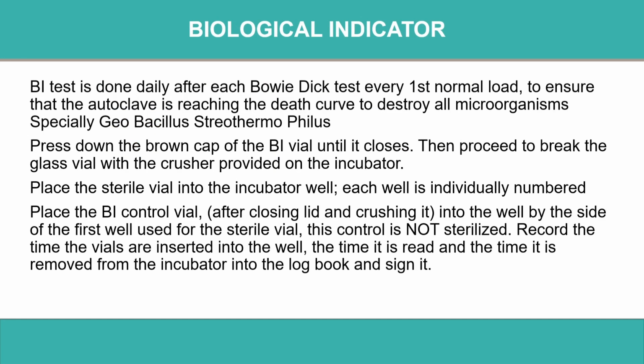These are the biological indicators. Actually, in the biological indicator there is a bacteria called Geobacillus stearothermophilus. This is a highly potent, highly heat-resistant bacteria that can tolerate heat. In the autoclave, the temperature goes above 134 degrees centigrade, and this is the bacteria that tolerates this heat. If we put it inside the incubator and the color does not change, it means it has died.